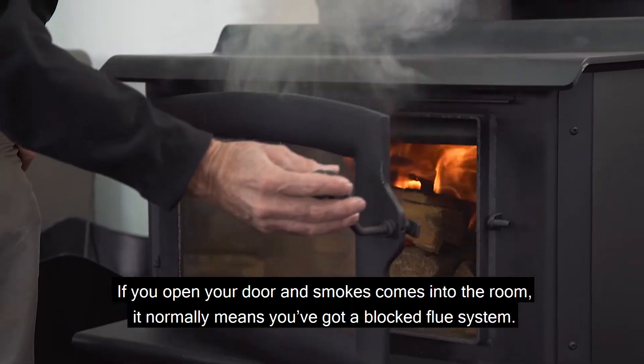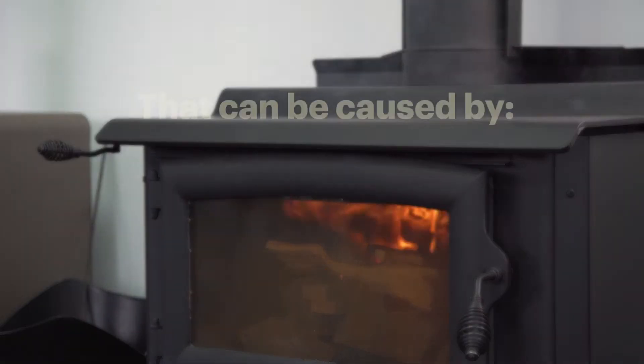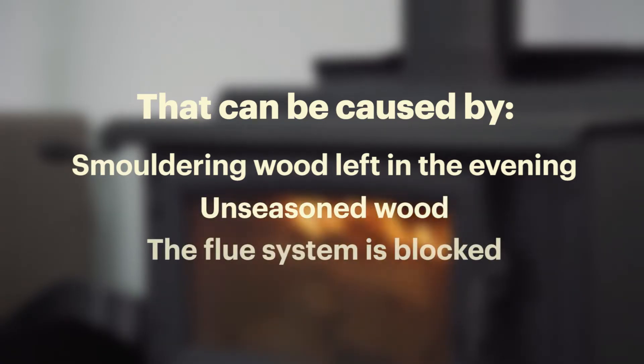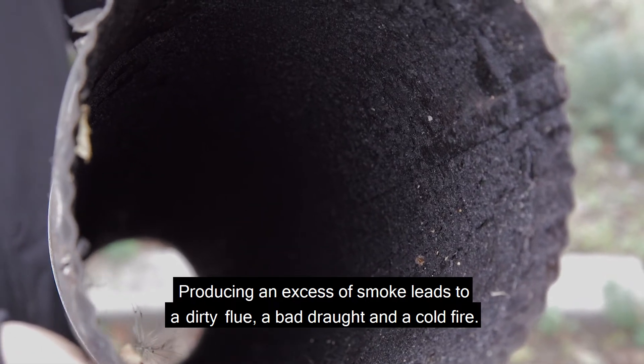If you open your door and smoke comes into the room, it normally means you've got a blocked flue system. That can be caused by smouldering wood left in the evening, unseasoned wood, but in all cases it means that the flue system is blocked. Producing an excess of smoke leads to a dirty flue and bad draft and a cold fire.